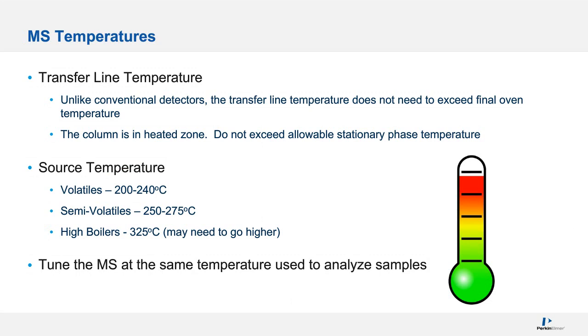Okay, the transfer line temperature doesn't have to be as hot, for instance, if you're doing ECD or FID work. The norm is to be 20 degrees higher than the final oven temperature. Well, because you have a big vacuum pulling on your compounds, you don't need the source and the transfer line to be that hot.